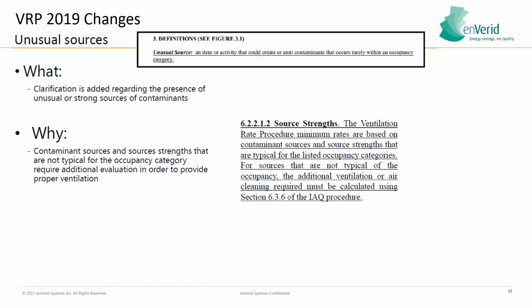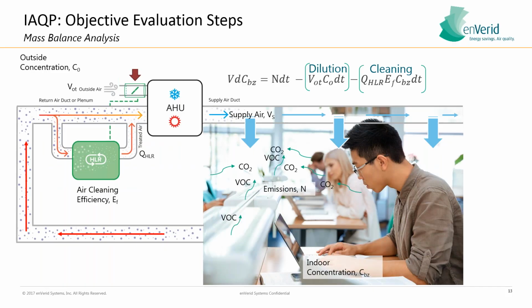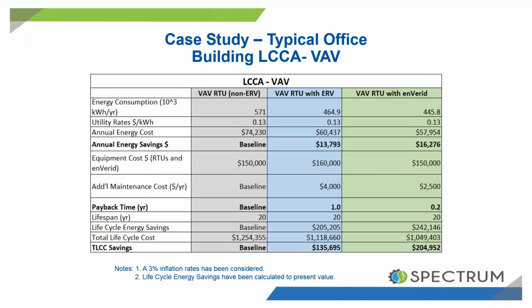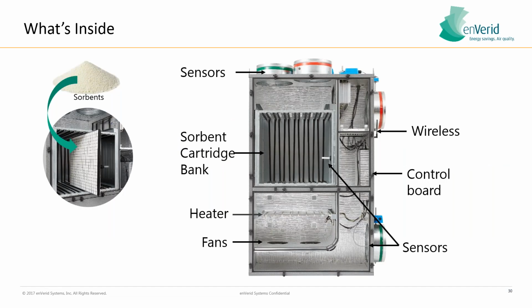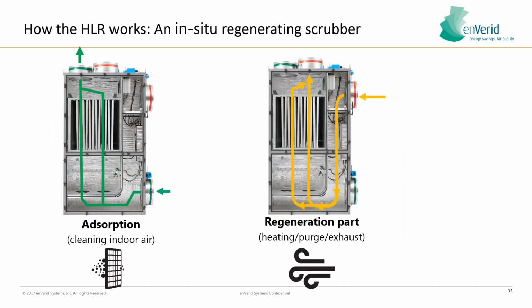Excellent. I just have a couple of additional case studies. I'm happy to expound on any additional information regarding the classification of air. I just want to revisit that question briefly to make sure I answered it fully. During the regeneration cycle, when you're purging the system of that regeneration air, no additional treatment needs to be done. That air is the same as any other exhaust air from within the space. It's not considered to be contaminated in any shape or form, so no post-treatment is required. It's just standard air with slightly elevated levels of CO2, same as any other indoor air that would be exhausted from the space that is not contaminated.